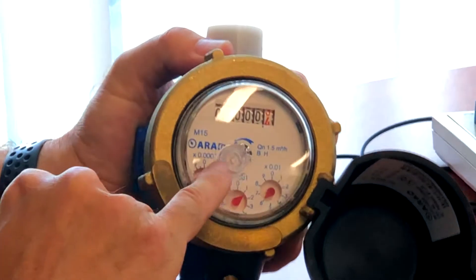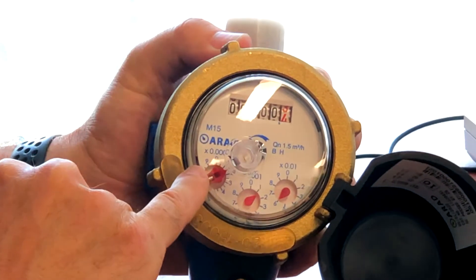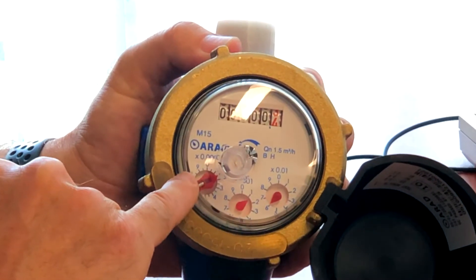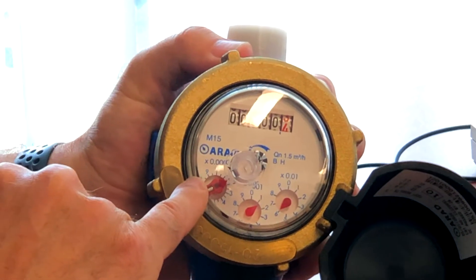Okay, as you can see where I removed the pulse cable, it's situated next to the leftmost red dial. Now what happens is when that red dial rotates, the water meter outputs one pulse. So how do we work out how many liters per pulse is generated from this water meter?